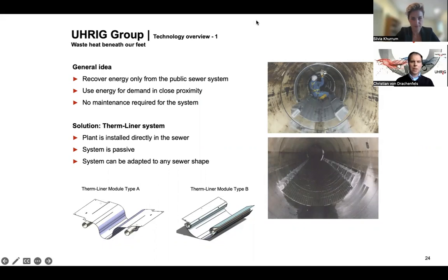And the idea is to supply building complexes or heat networks that are in rather close proximity to the sewer pipe. This could still be a couple of hundred meters. It always depends on the size of the project and on the energy demand. Of course, if you have a huge energy demand, it is also economically viable if you go for a longer connection line to the heating central, to the heat pump.